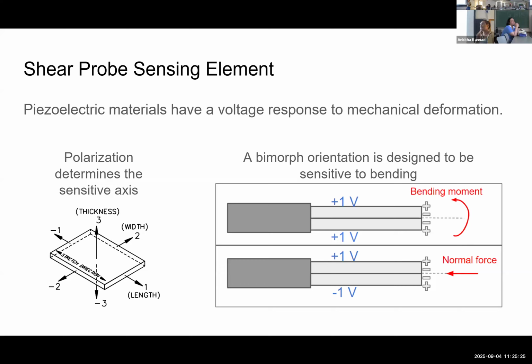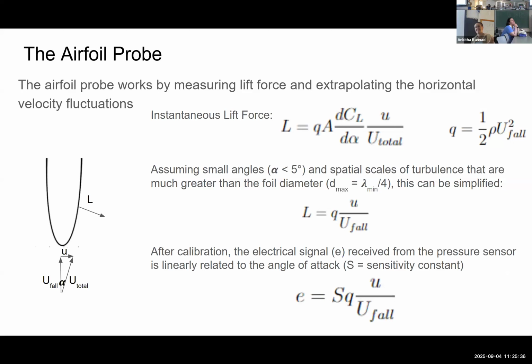Yeah, yeah. And the idea of that is that as your profiler is dropping through the water, you're really looking to measure the shear, which is du/dz. So maybe that is better to look at this diagram. So the way that this bimorph works, we're sensitive to bending moment. If this is the shape of the probe, we are measuring the lift force on the outside of this. So kind of the same way an airplane wing works, the fluid flowing over the shape is going to create pressure gradients. This is labeled as an L because it's the same math that gives you lift that lifts up an airplane. So because of the differential pressure gradient, if you have a slight angle in your fluid, there's going to be higher pressure on this side and lower pressure on that side.